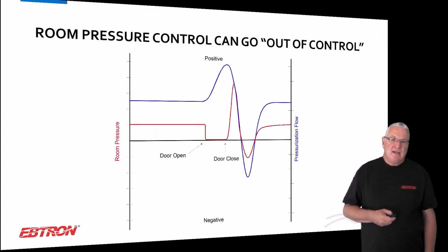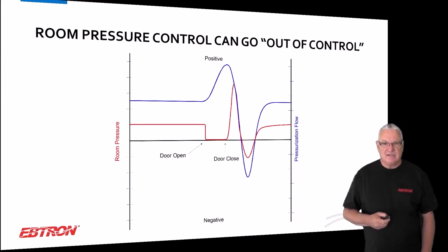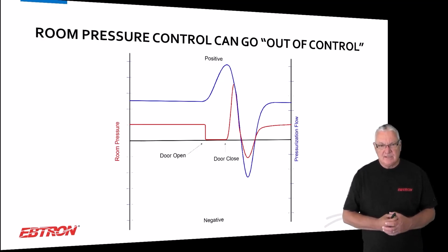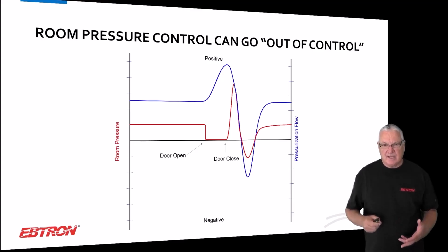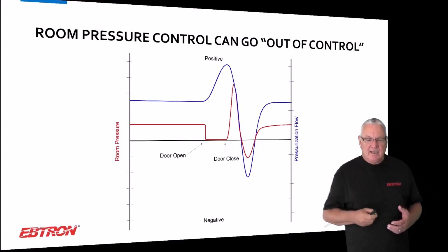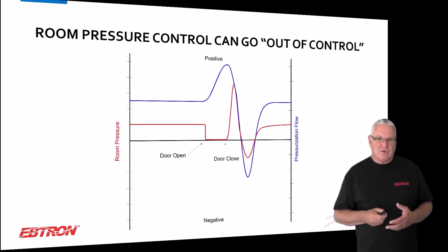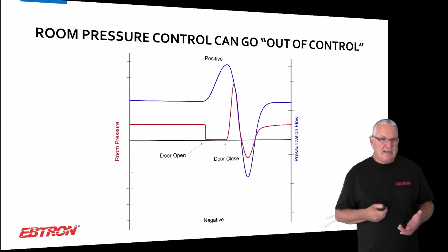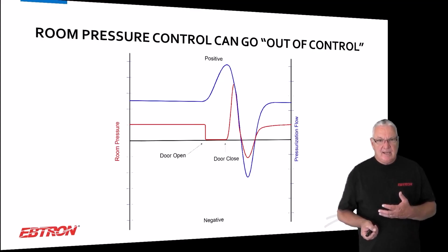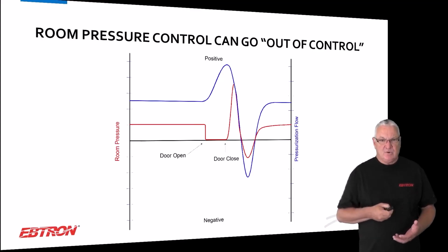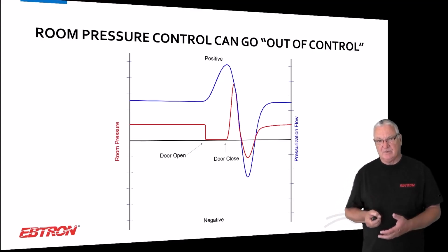Another thing is, and this is just a can go, doesn't mean it has to, okay? I mean, a lot of this is a tuning thing, but one of the problems when you do room pressure control is, and this is keeping it kind of simple, okay, what we're looking at is the room pressure is the red, and the pressurization flow is the blue. When you do pressure control and you open a door, it can go out of control, okay? And if you had a positive pressure space like this one, it could instantaneously turn into a negative pressure space.